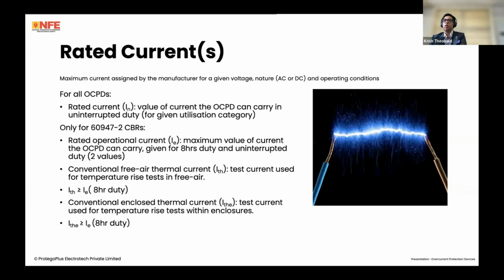When it comes to rated currents, all overcurrent protection devices have a rated current IN. This is similar to the rated operational voltage. It's the value of current the overcurrent protection device can carry in uninterrupted duty, which means being able to carry it constantly throughout its lifespan. When it comes to 60947 Part 2 circuit breakers, CBR denotes circuit breakers, just so you know, you have a rated operational current IE, which is the maximum value of current that overcurrent protection devices can carry. And these are given for two duty cycles. The first is an 8-hour duty, and the second is an uninterrupted duty.